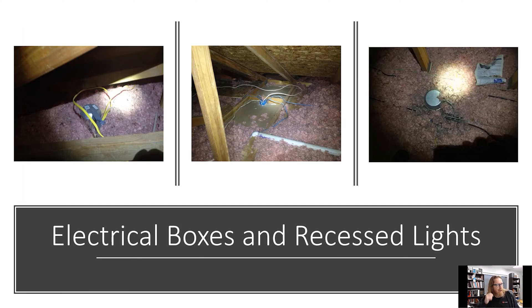Here's something else we see a lot: recessed lights covered by insulation. Some of them are IC rated, some of them are not IC rated. We've also got plumbing being covered over by insulation — nobody even knows it's there. So if you're ever trying to step on things, be careful. You don't want to crack that plumbing line. That could be a drain from HVAC or an exhaust from the plumbing system. We also have boxes that feed into electrical outlets and things like that.